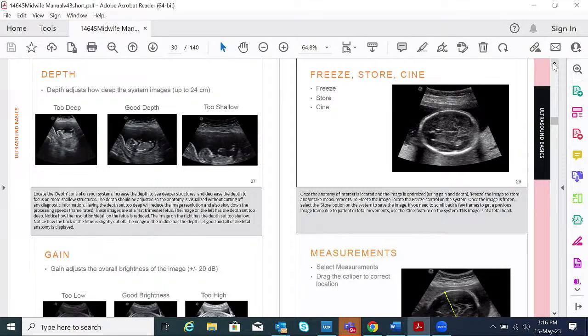Do your measurements accordingly. So once the anatomy of interest is located and the image is optimized using gain and depth, freeze the image to store and or take measurements. To freeze the image, locate the freeze control on the system. Once the image is frozen, select the store option on the system to save the image. If you need to scroll back a few frames to get a previous image frame due to patient or fetal movement, use the cine feature on the system. This image is of a fetal head, the above image.